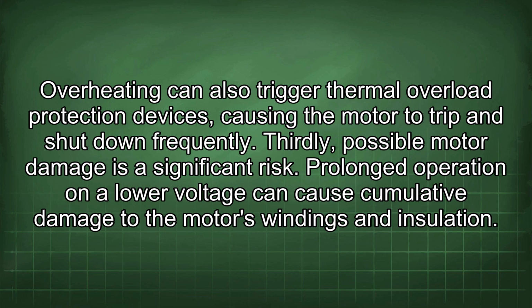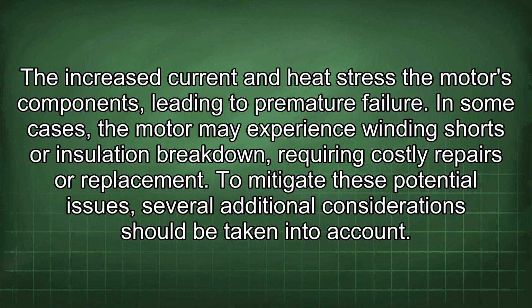Thirdly, possible motor damage is a significant risk. Prolonged operation on a lower voltage can cause cumulative damage to the motor's windings and insulation. The increased current and heat stress the motor's components, leading to premature failure. In some cases, the motor may experience winding shorts or insulation breakdown, requiring costly repairs or replacement.